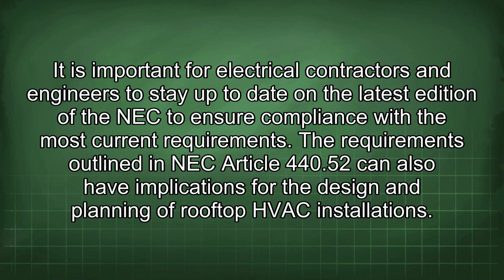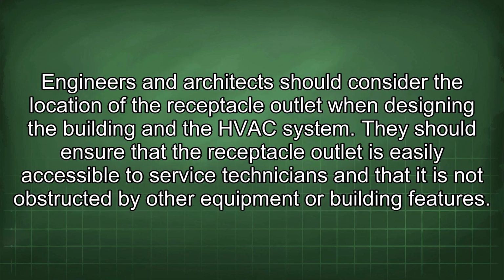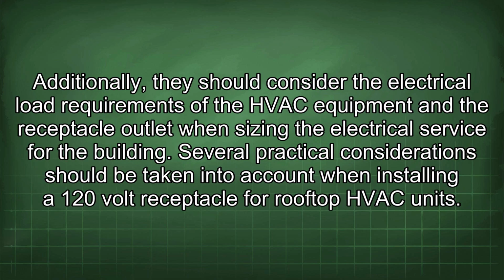The requirements outlined in NEC Article 440.52 can also have implications for the design and planning of rooftop HVAC installations. Engineers and architects should consider the location of the receptacle outlet when designing the building and the HVAC system. They should ensure that the receptacle outlet is easily accessible to service technicians and that it is not obstructed by other equipment or building features.